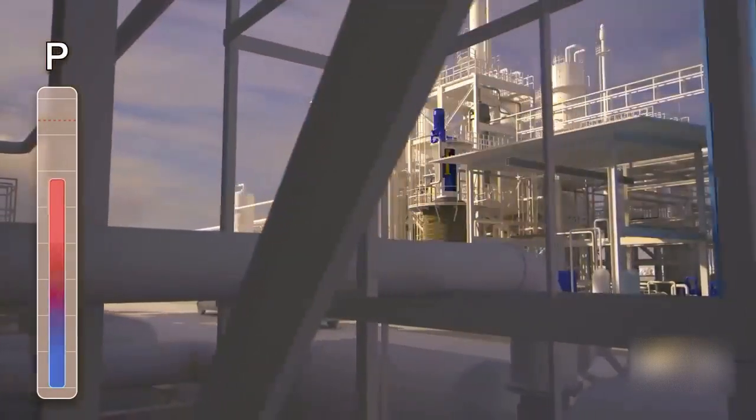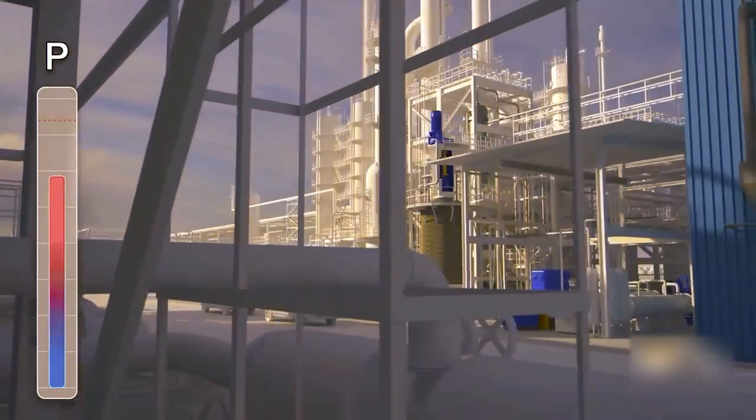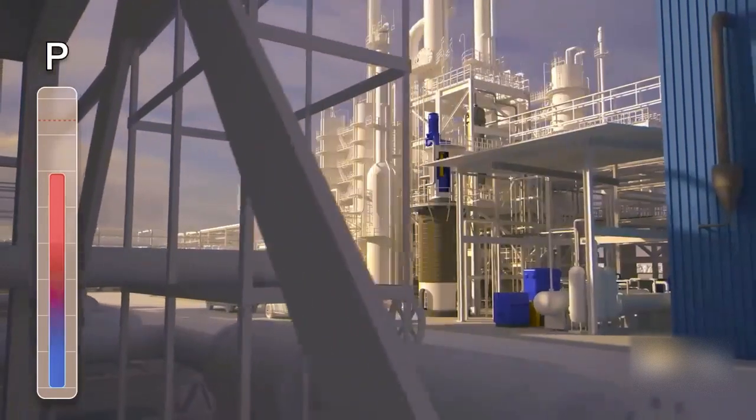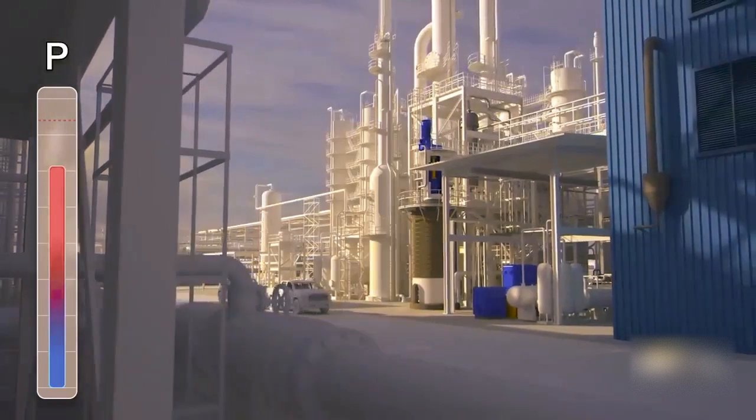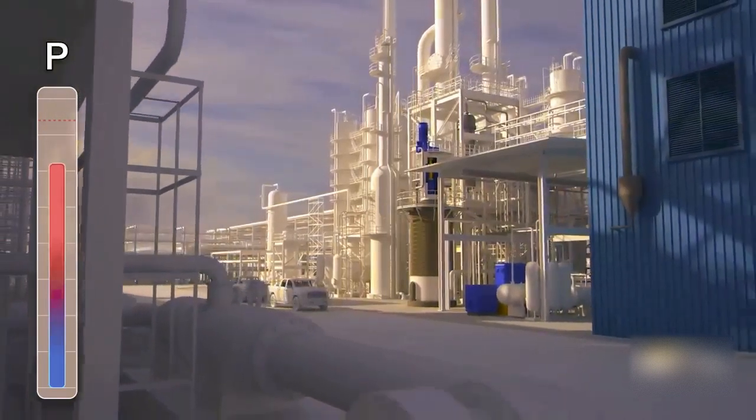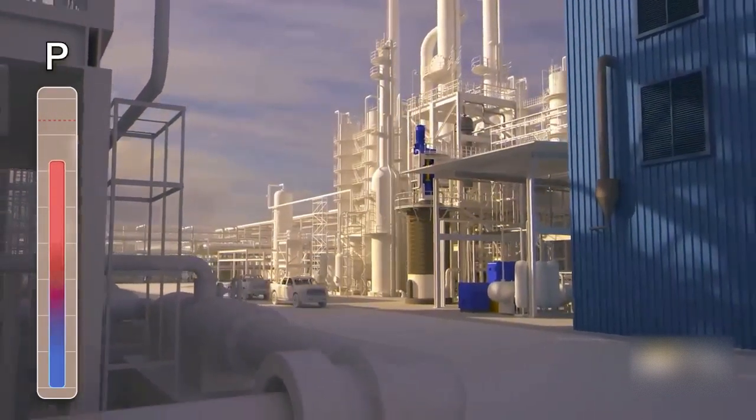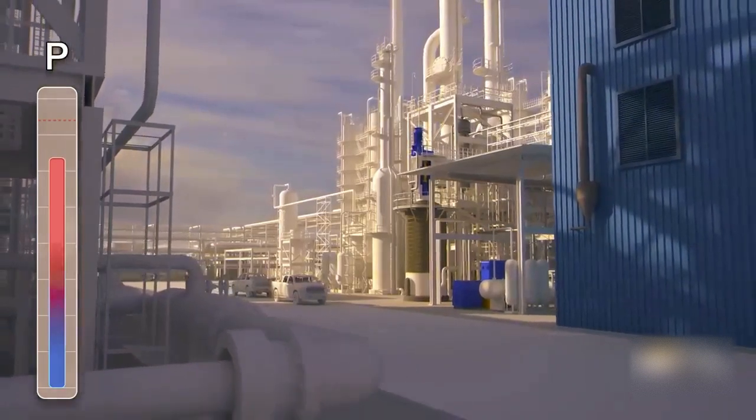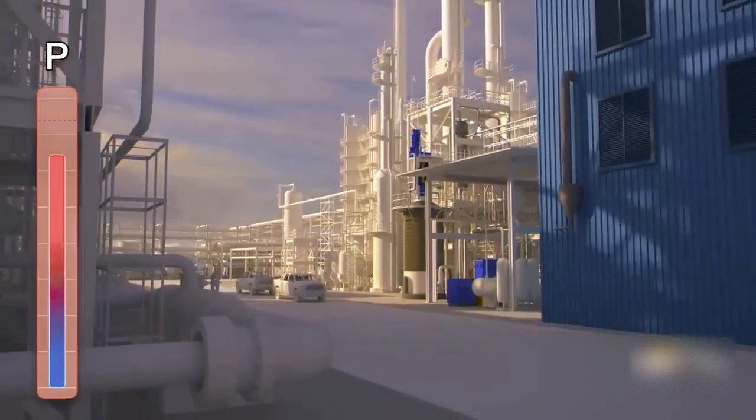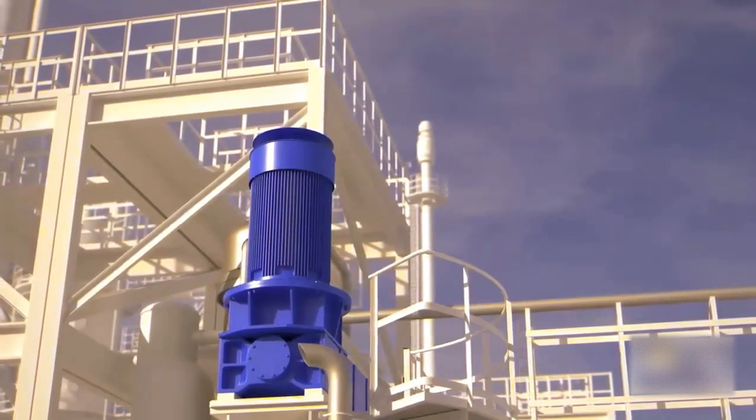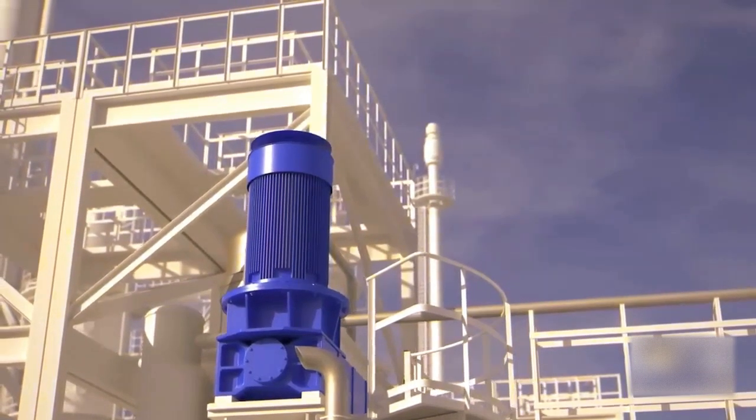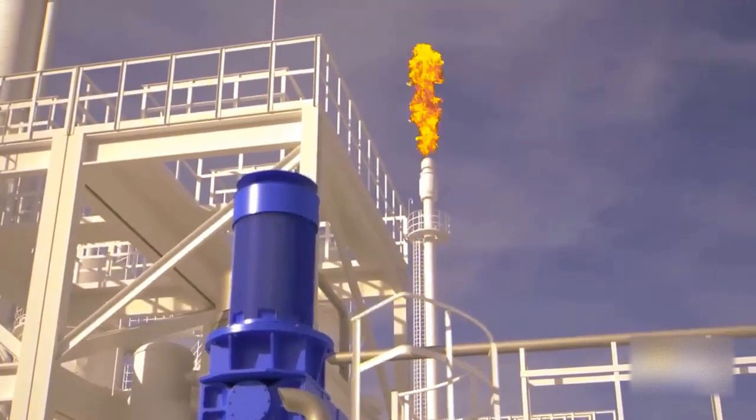By about 8:45 a.m., the reactor reached the target operating pressure of nearly 600 PSI, but pressure continued to increase. Around 9 a.m., the pressure reached 640 PSI, and the high pressure alarm went off. A board operator responded by periodically opening a pressure control valve to send some of the vapor inside the reactor to a flare.